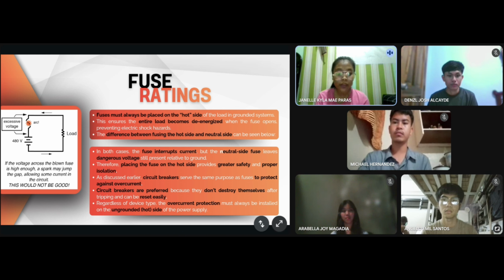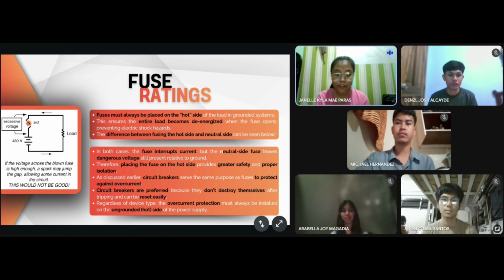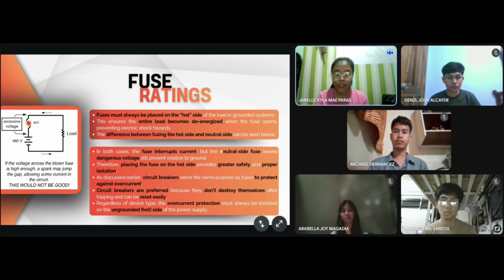So, here we have fuse ratings. We must always put the fuse on the hot side of the circuit. This is important because when the fuse opens, the whole load becomes de-energized, making it safer and avoiding electric shock. If the fuse is placed on the neutral side, the current may stop, but there is still dangerous voltage present. So it is still risky. That is why we place the fuse on the hot side for proper isolation.